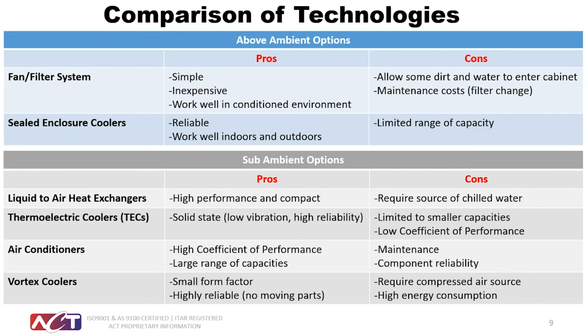Enclosure air conditioners, on the other hand, offer a high coefficient of performance and the ability to address a wide range of heat loads. The downside is that AC systems are known to have long-term reliability issues, and regular maintenance is required to keep the system running at full performance.